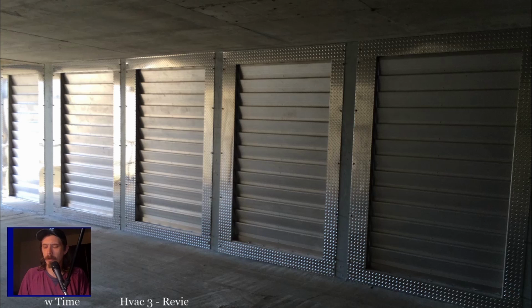Some of them are going to be automatically controlled by coils, right? So they're magnetically controlled. So you have two connections. You have the control side connection and the load side connection, whatever that may be, even if it's still on the control circuit. But when I'm trying to troubleshoot, I generally just think of all that stuff as switches. A relay is a switch, contactors a switch, thermostats are just switches. It helps me not get too bogged down with what exactly it is.